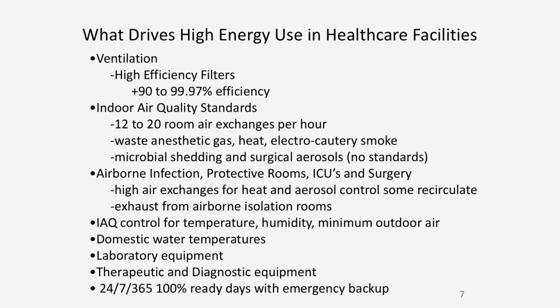So what drives high energy use in healthcare? Right on top is ventilation. It's mainly because we insist that we highly filter that environment. If you look at the total industry, we really are an industry that has highly filtered buildings, way higher than what we see in most of our commercial space. In addition, our indoor air quality standards generally mean we have to have 12 to 20 air changes per hour.